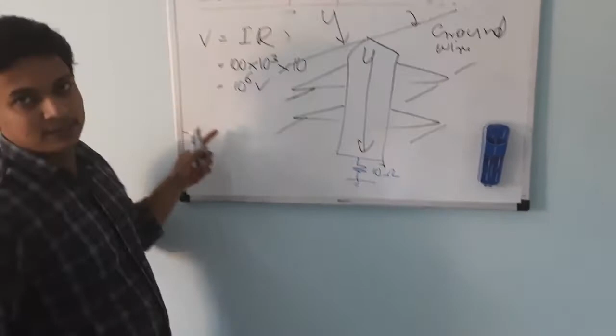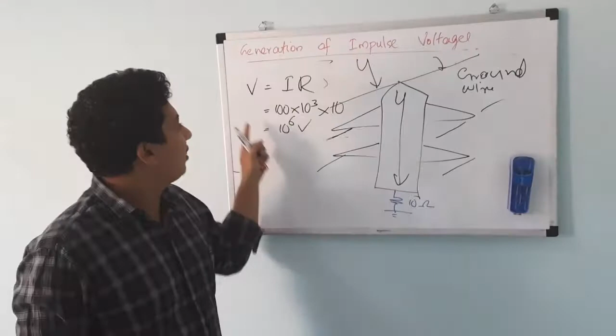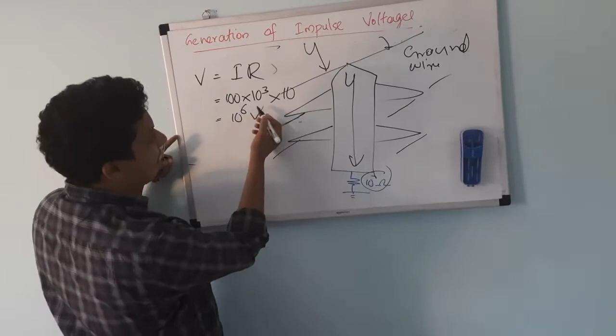Voltage is given by current into resistance. The current is 100 kilo ampere, so 100 into 10 power 3 into the 10 ohms. That comes to around 10 power 6 volts, around 1 million volts, coming to this tower when you have 100 kilo ampere and 10 ohm resistance. So this is equal to around 1000 kilovolt.